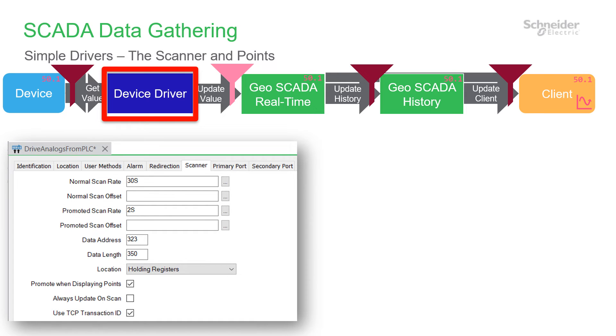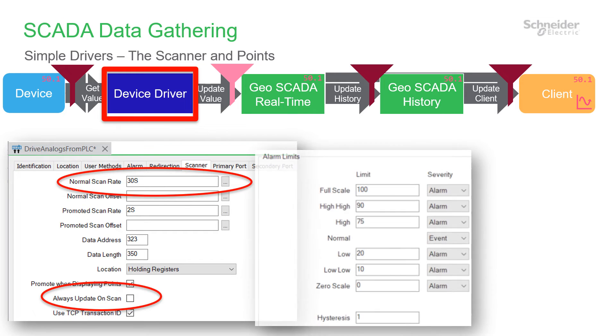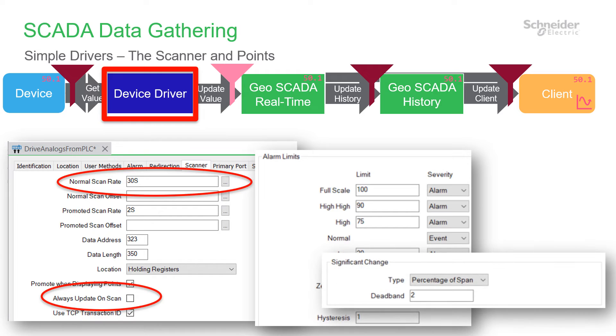Starting with the simple driver, let's look at the scanner. You'll want the normal scan rate to be fast enough for operators to respond to alarms. You don't need to select the Always Update on Scan checkbox, unless you need the scanner statistics to update every scan, which could be a resource problem. For digital points, there's usually nothing extra to configure — you'll get to see state changes and there are no timed reports. For analog points, you need to set the alarm thresholds so you know when the value crosses them. Also, you configure significant change so you can see when the value moves. Note that for these percentage fields, enter 1 for 1%, not 0.01.